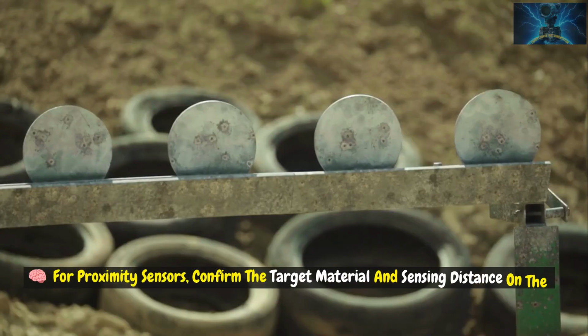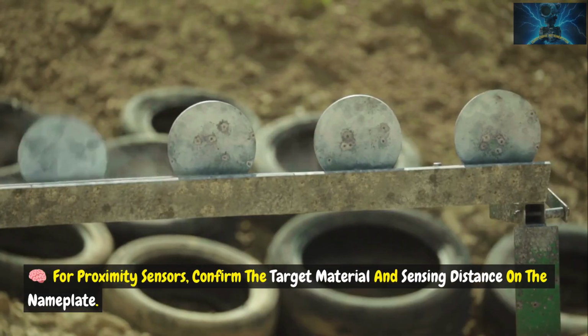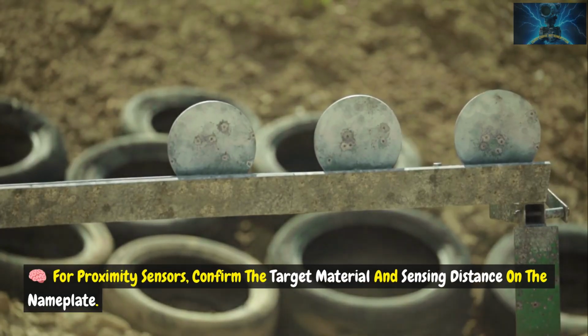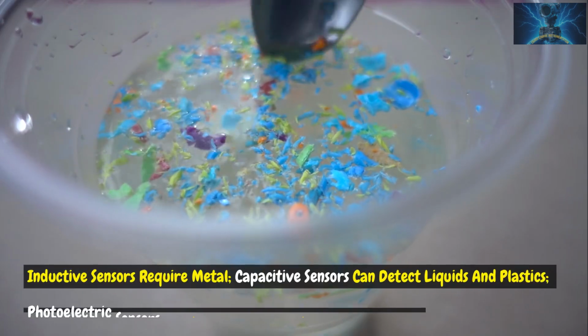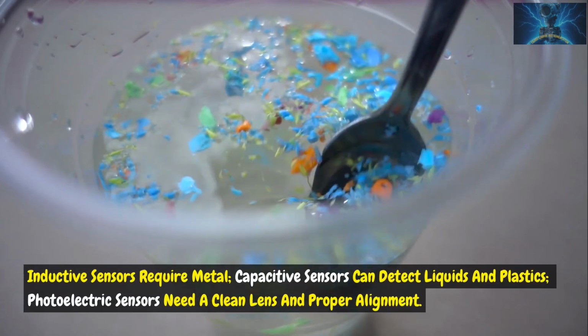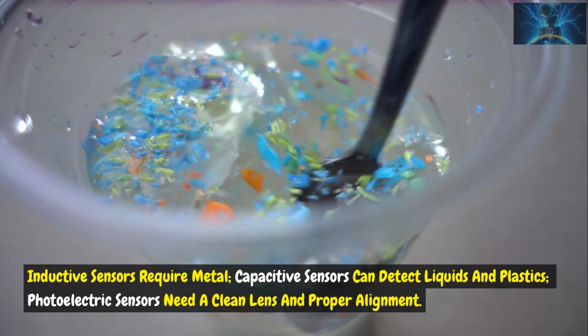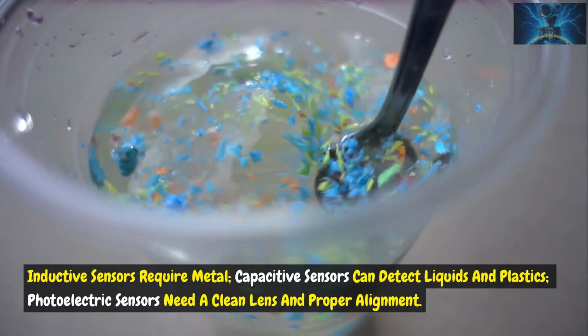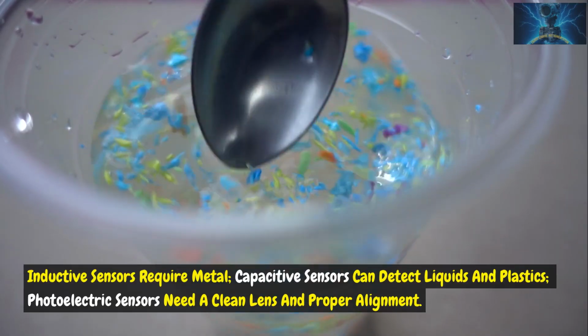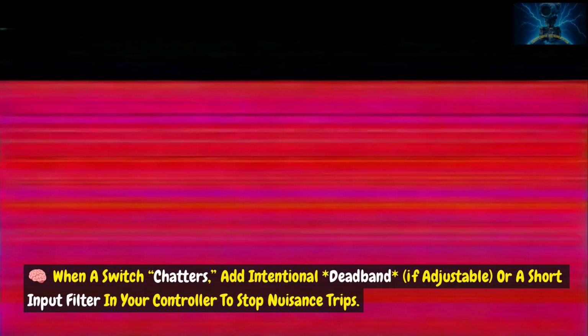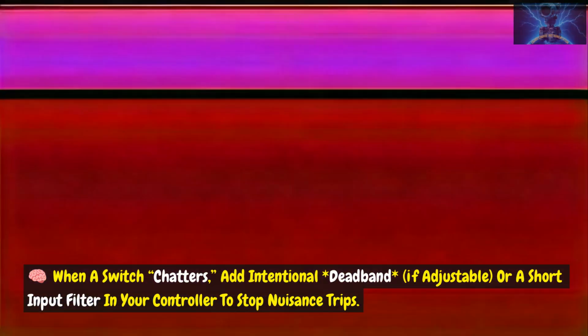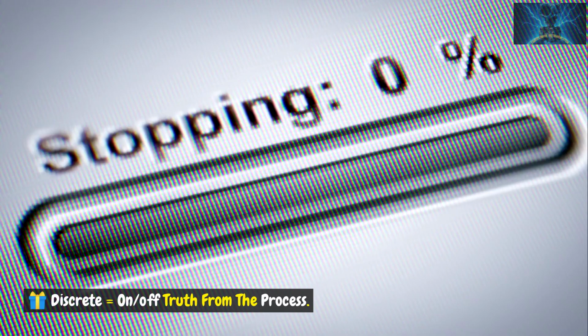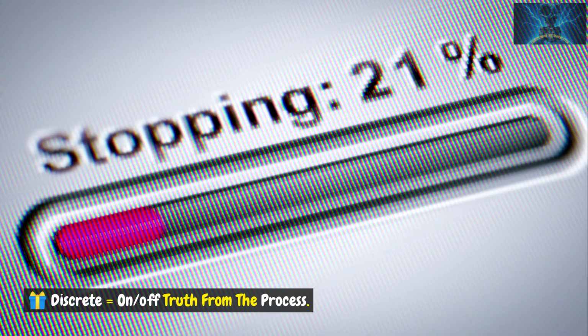For proximity sensors, confirm the target material and sensing distance on the nameplate. Inductive sensors require metal. Capacitive sensors can detect liquids and plastics. Photoelectric sensors need a clean lens and proper alignment. When a switch chatters, add intentional deadband, if adjustable, or a short input filter in your controller to stop nuisance trips. Takeaways, discrete and on-off truth from the process.